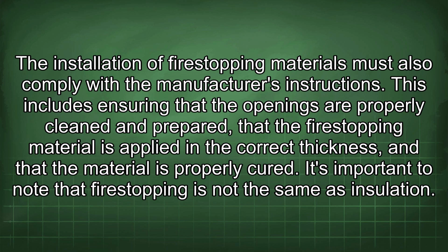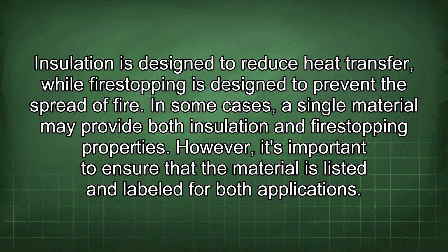The installation of fire-stopping materials must also comply with the manufacturer's instructions. This includes ensuring that the openings are properly cleaned and prepared, that the fire-stopping material is applied in the correct thickness, and that the material is properly cured. It's important to note that fire-stopping is not the same as insulation. Insulation is designed to reduce heat transfer, while fire-stopping is designed to prevent the spread of fire. In some cases, a single material may provide both insulation and fire-stopping properties. However, it's important to ensure that the material is listed and labeled for both applications.